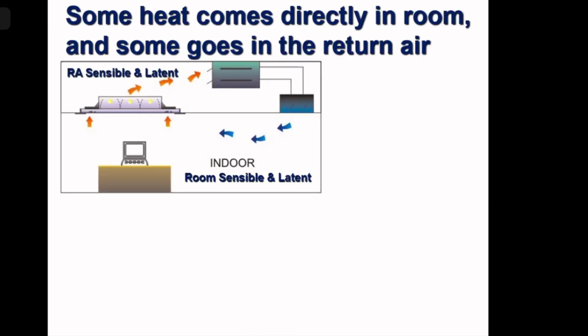Last slide, we said that some heat is generated within the room, and some heat comes from outside into the room. We have also discussed supply air, and we have also discussed return air. Now we have to understand that the whole of the heat is not coming within the room straight away. Some heat is coming straight away within the room, and some heat is coming in the return air portion of the room. So this is a room we have shown.